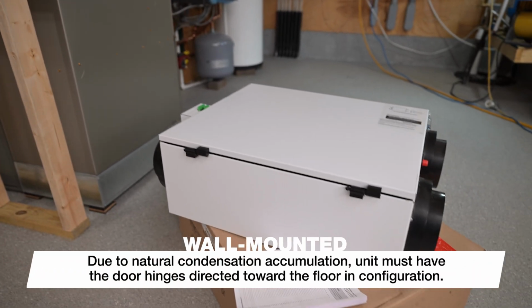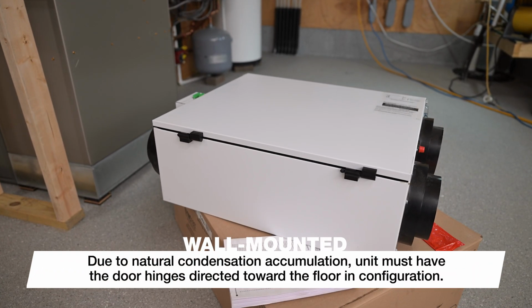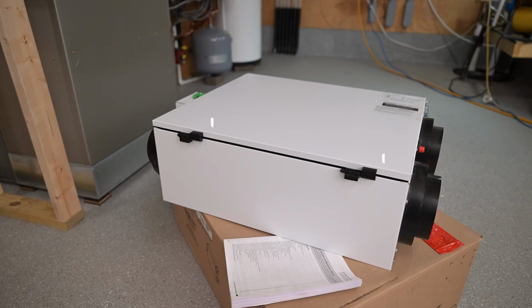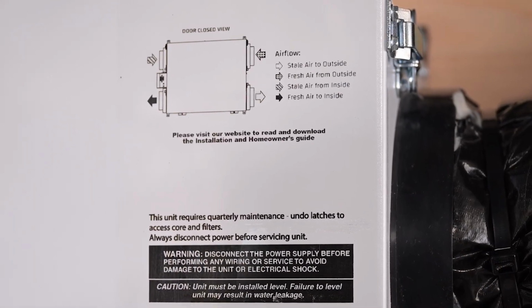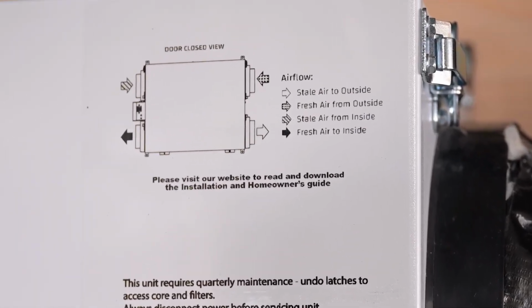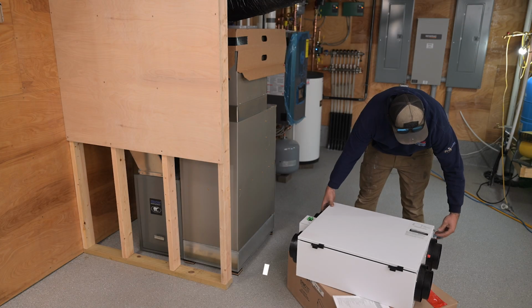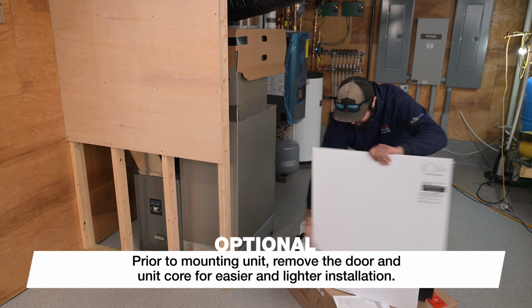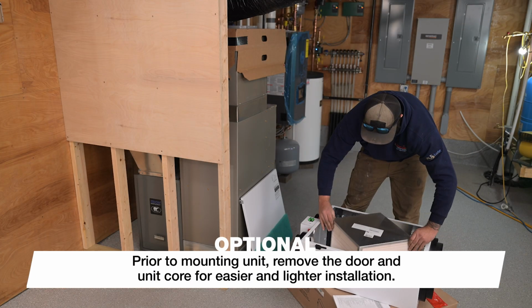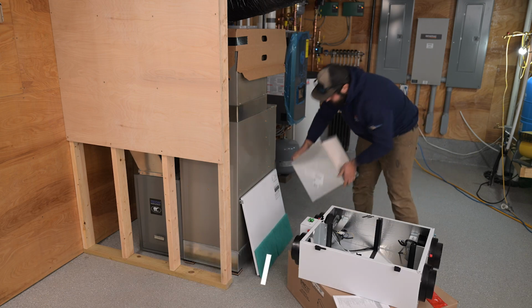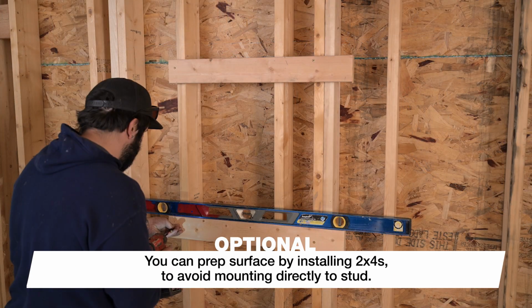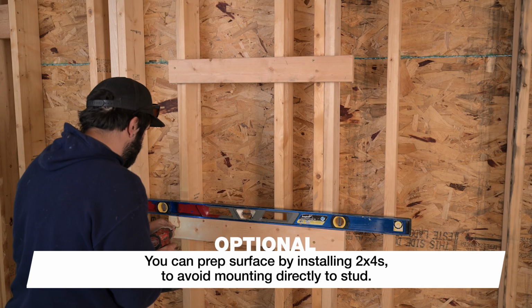It is important to note that due to natural condensation accumulation, the unit must have the door hinges directed toward the floor in the wall mount configuration. Please refer to the image included on the door panel to ensure proper orientation. Before mounting the unit, you can easily remove the door and the unit's core to make it lighter to install. If needed, you can also prep your surface by installing 2x4s across the wall studs so you don't have to mount directly to the stud.